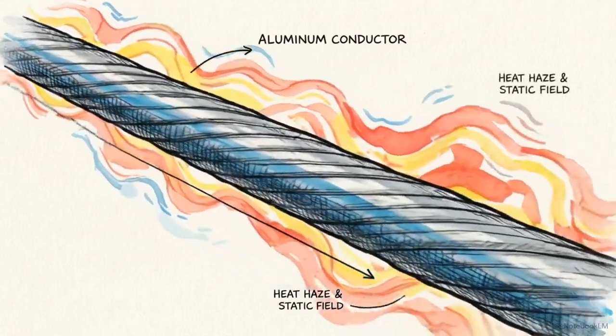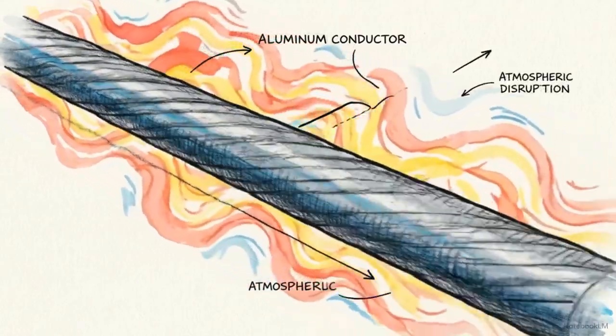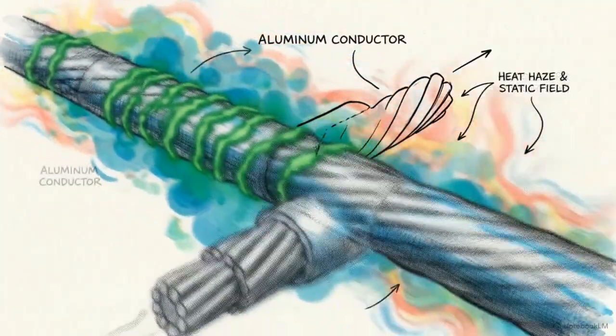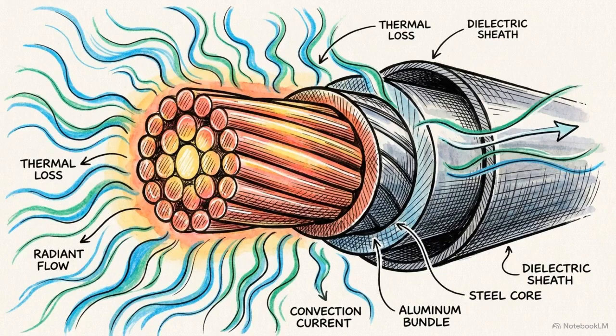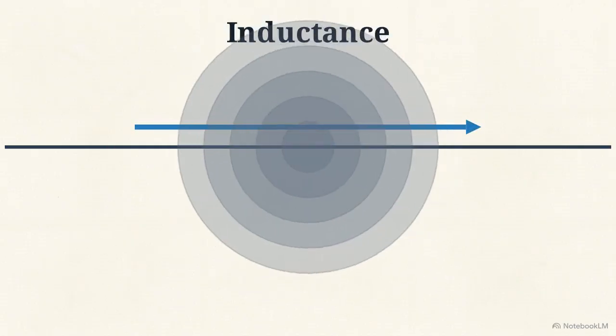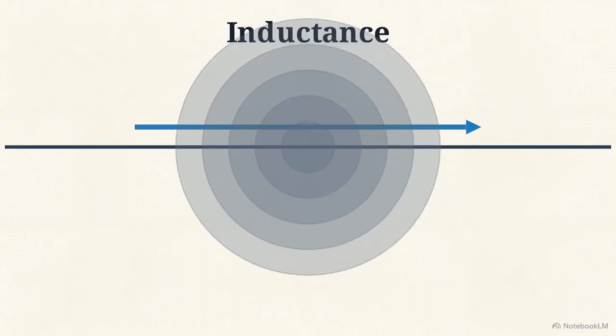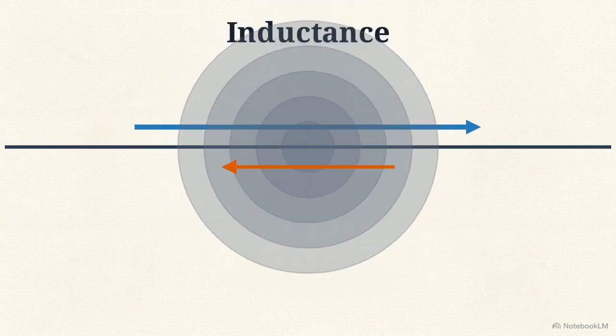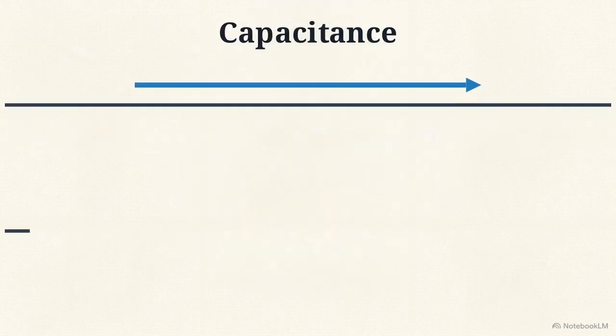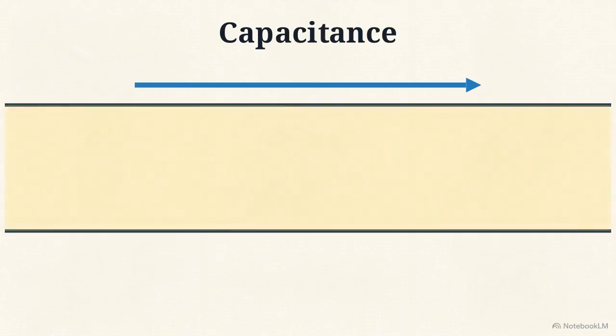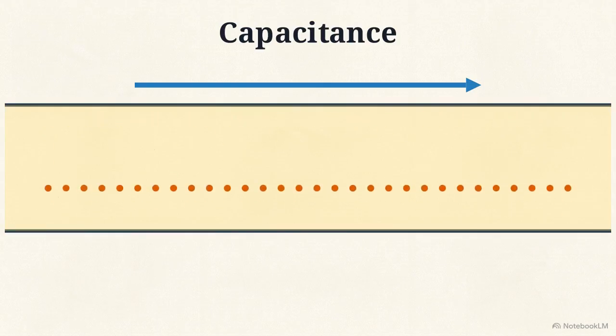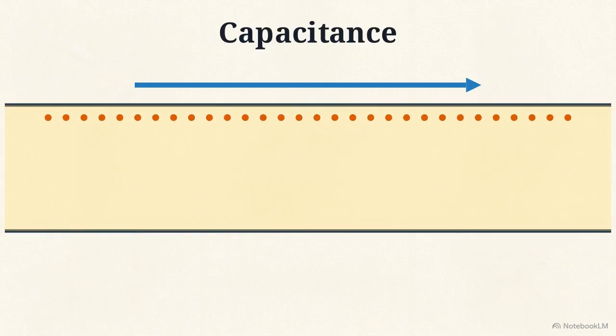The wire itself and the air surrounding it actively resist the flow of current through three distinct parameters. The first is resistance. The physical material of the wire constantly converts a portion of the electrical energy into heat. The second is inductance. Because the current is alternating, it creates a fluctuating magnetic field around the conductor. That field induces a secondary voltage that pushes back against the forward flow. The most complex force is capacitance. When two conductive wires are separated by open air, the space between them stores an electric charge. This draws a charging current, creating reactive power that moves through the lines even when no homes are pulling electricity.